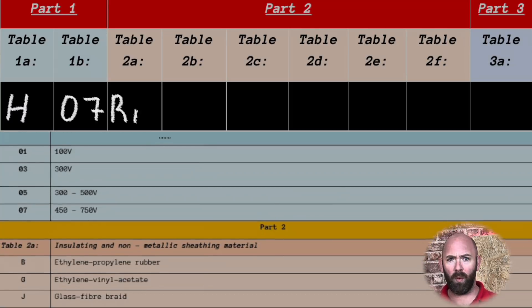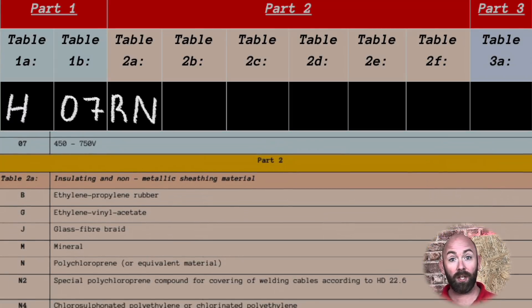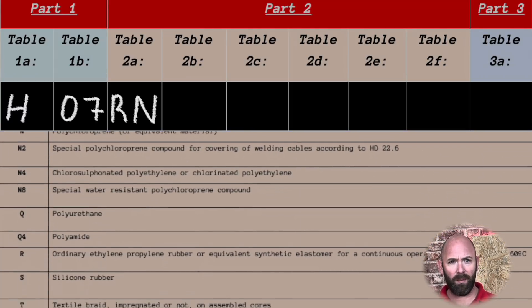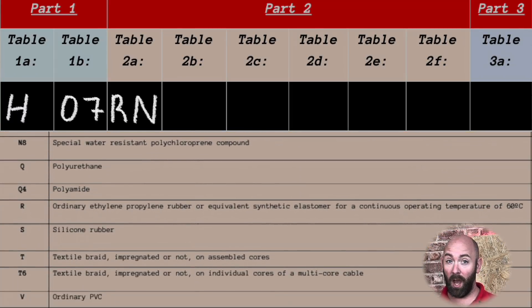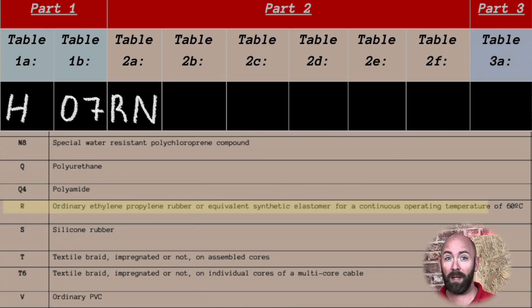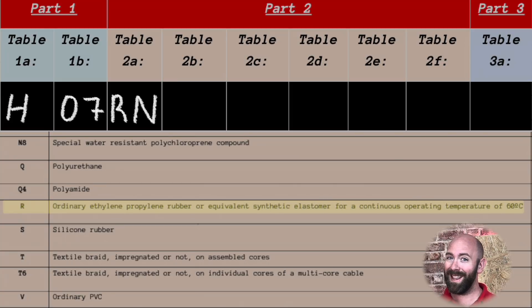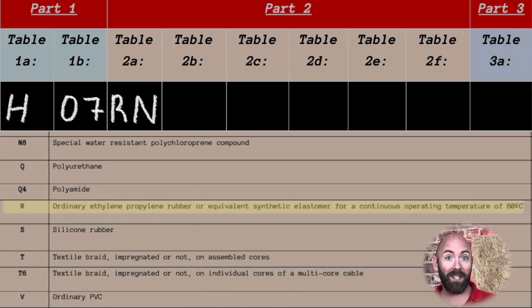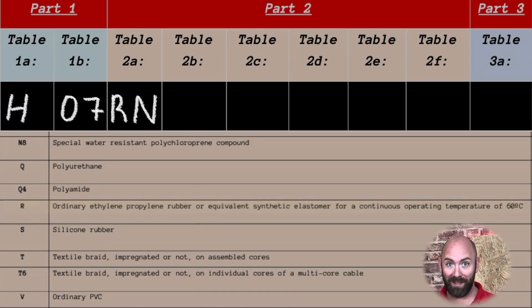We now have the letter R, which is the insulation around the conductor. Navigating the table we can see that this code is for an ordinary ethylene propylene rubber, or equivalent synthetic elastomer, for a continuous operating temperature of 60 degrees Celsius.